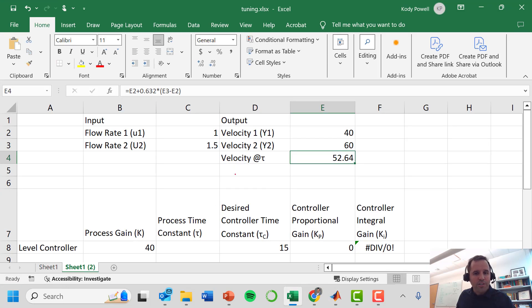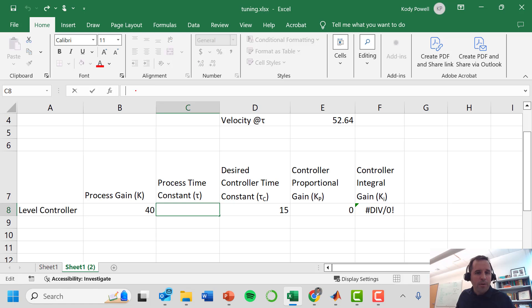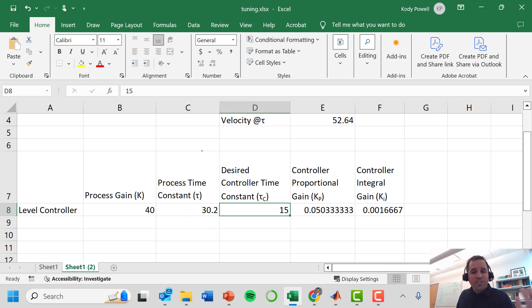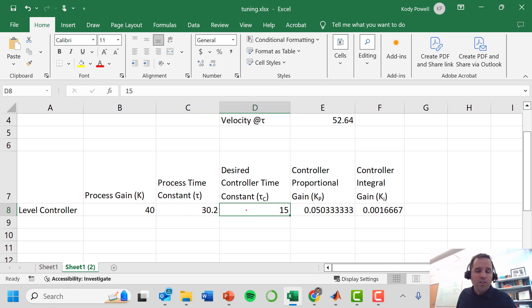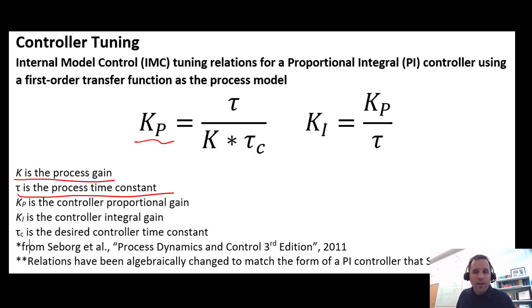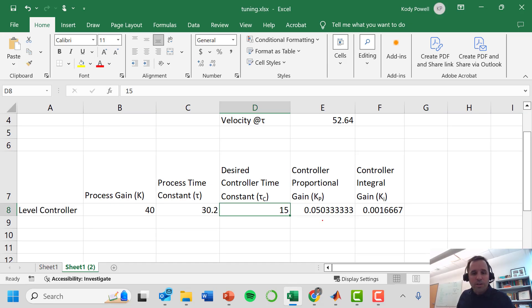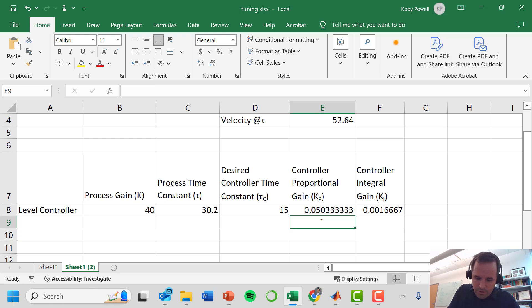Back in the calculation spreadsheet, we enter the process time constant as 30.2 seconds. The IMC tuning relationships are already built in. We select a desired controller time constant of 15 seconds — speeding up the process from 30 seconds. Running the tuning relationships, we get kp = 0.05 and ki = 0.0017.